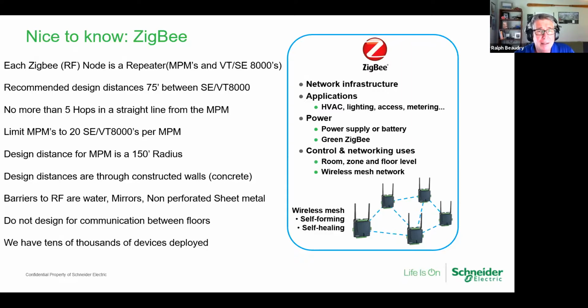Each gateway and each node on the network, so each SE8000, is a repeater. Recommended design distances between SE8000s or VT8000s is 75 feet. That's design, right? It will communicate further, right? Every device is a repeater. We recommend that you go no more than 5 hops in a straight line. So 75 feet, 75 feet, 75 feet, right? When you're 5 hops out, don't go any further. You can, but again, you're going to have all kinds of lag time that you're going to start creating on the network.